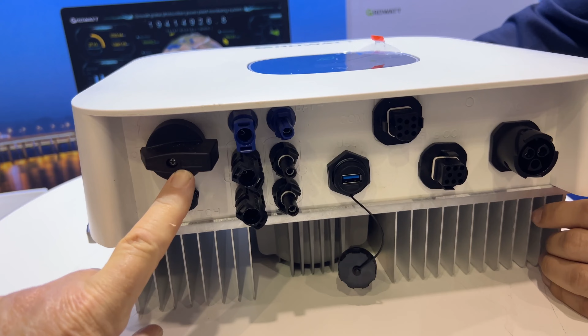DC isolator is already certified under AS/NZS 60947.3 - both inverter and the DC isolator together. It's not separated; before it was separated, and that wasn't allowed. Right now it's together, both inverter and DC isolator combined. We're finishing that one, and it's totally qualified as the inbuilt DC isolator in Australia and New Zealand. No problem, go for it. Well done, because that's a big challenge for a lot of inverter manufacturers to get the combined tests done on their products. Compliant DC isolator, love it.